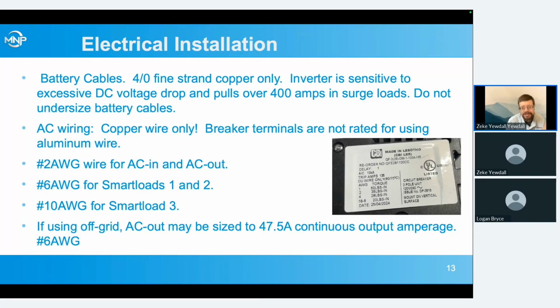Electrical installation. We see a lot of installs done with undersized cables, and that can cause a lot of poor performance of the system. Battery cables, we want 4/0 fine strand copper cables only. The inverter is pretty sensitive to excessive voltage drop from the batteries.